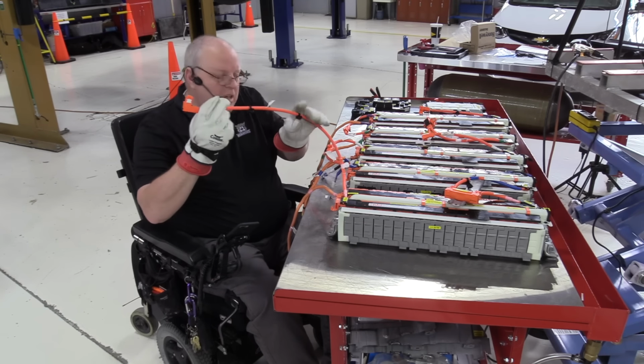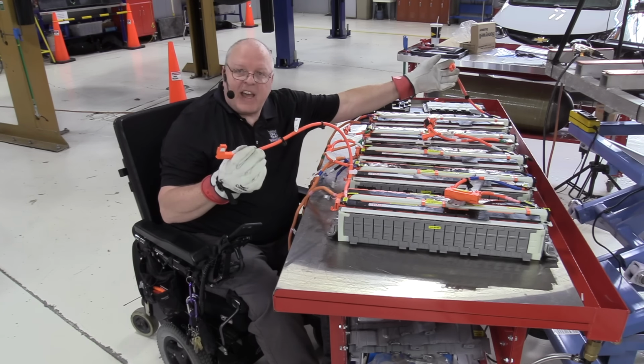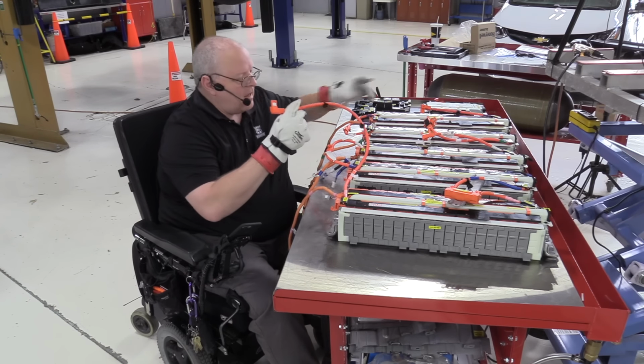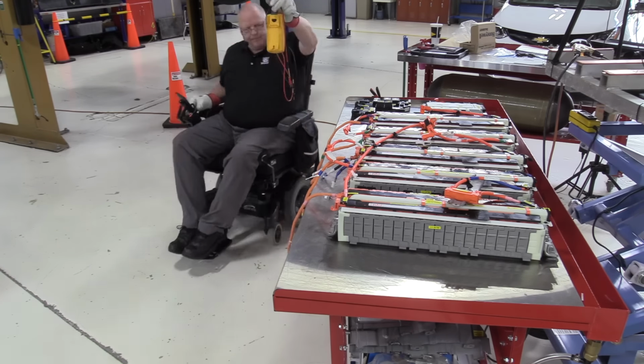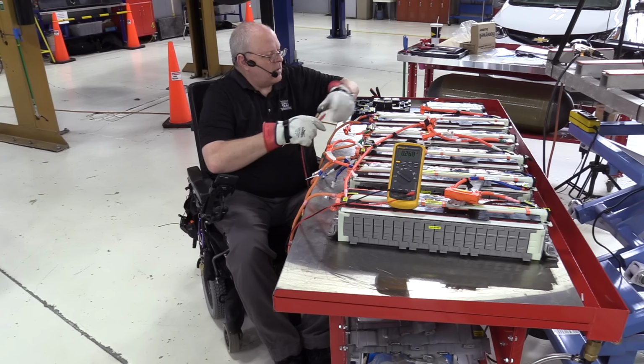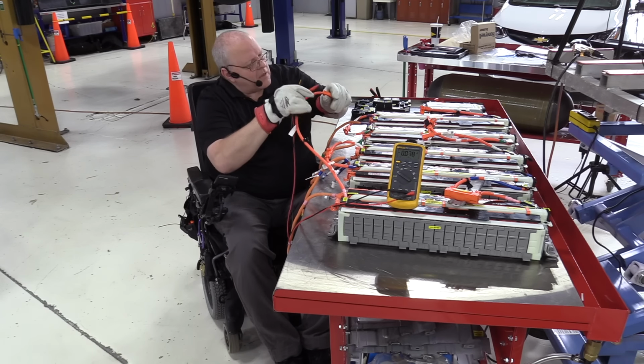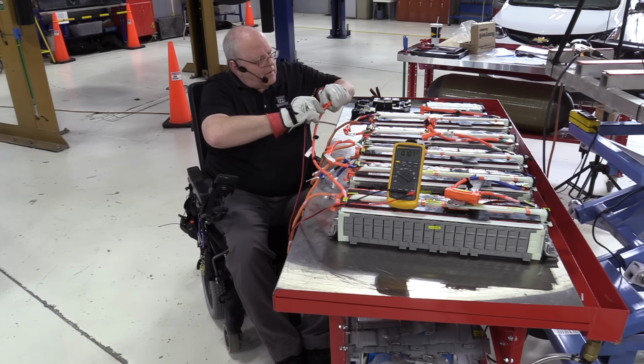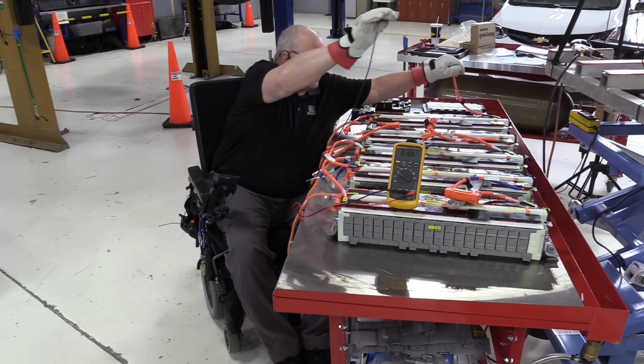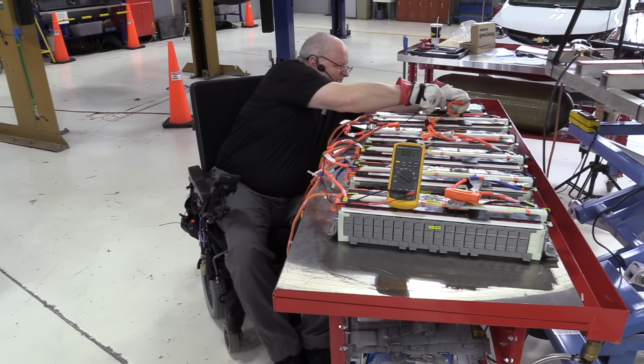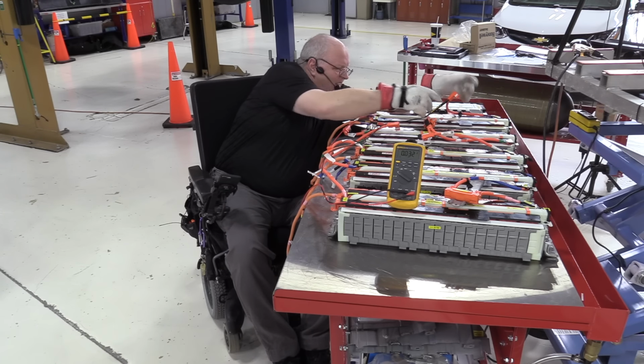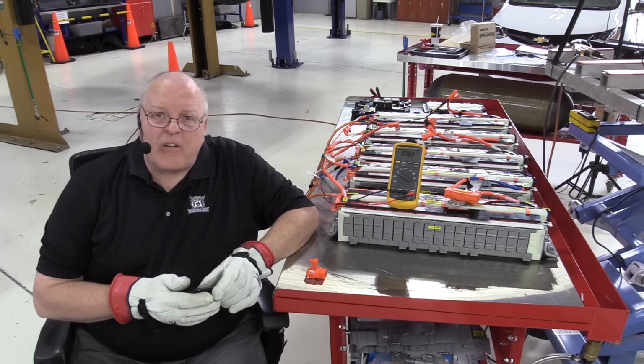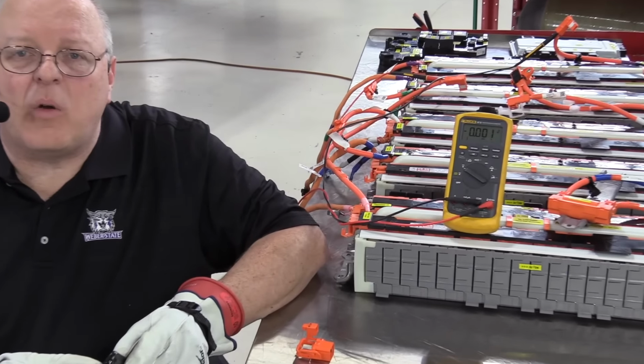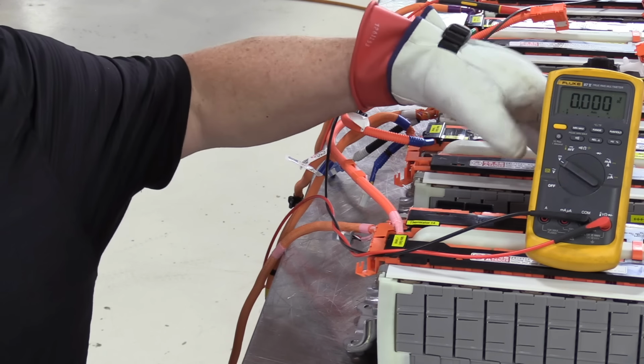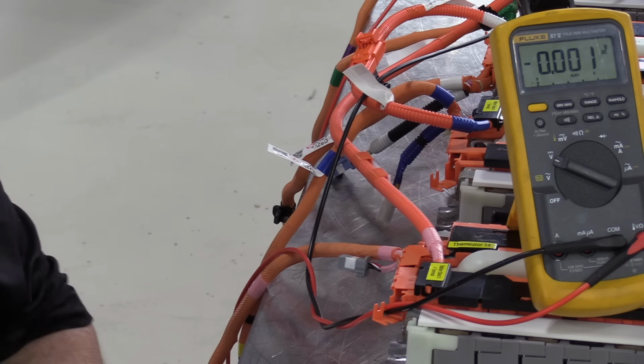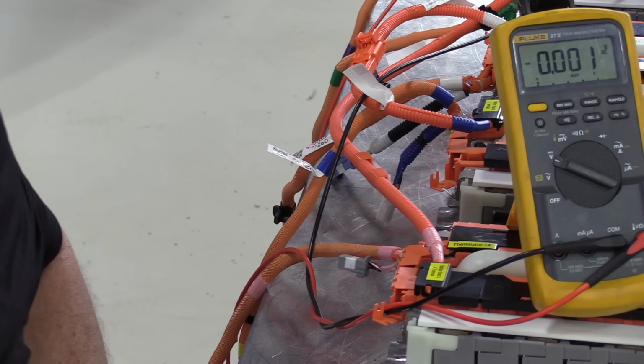Battery stack number 5's positive cable and battery stack number 1's negative cable should give us the 350 volt total battery voltage. If I measure from the positive terminal of battery stack number 5 to the negative terminal of battery stack number 1, and if everything was wired in series, our multimeter would read 350 volts. But as you can see, it is not—it's reading pretty much 0 volts.